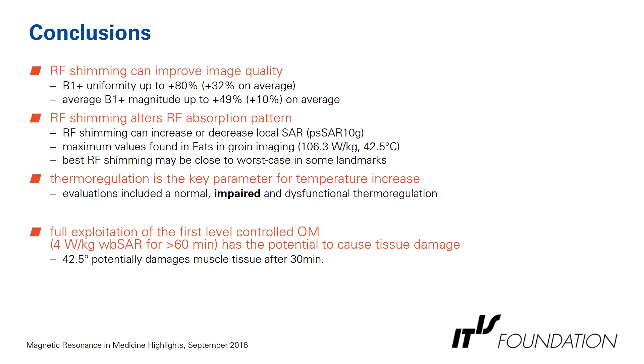In conclusion, RF shimming can improve image quality — B1+ uniformity can increase by up to 80% and average B1+ magnitude by up to 50%. However, RF shimming alters RF absorption patterns and can increase or decrease local SAR. Maximum values are found in Fats in groin imaging at 106 W/kg. The best RF shimming may actually be close to worst-case SAR in some landmarks. Thermoregulation is the key parameter for temperature increase. Full exploitation of the first-level controlled operating mode has the potential to cause tissue damage, since 42.5°C for more than 30 minutes has the potential to damage muscle tissue.